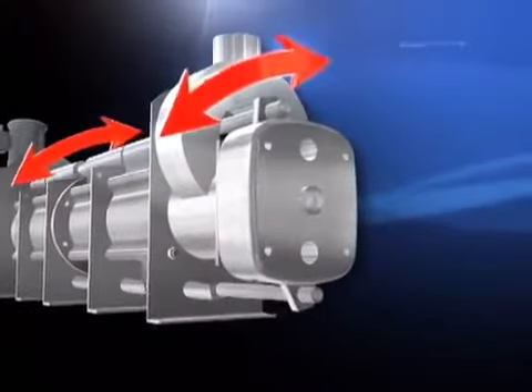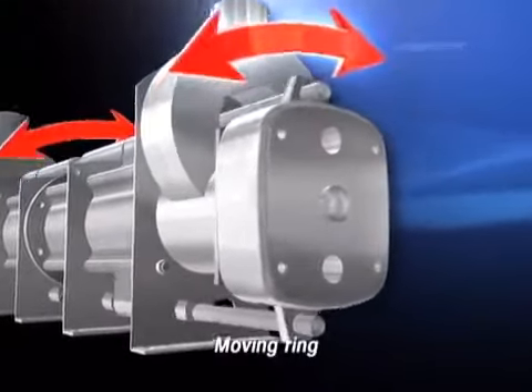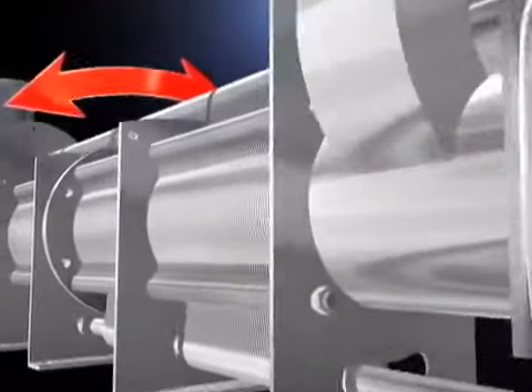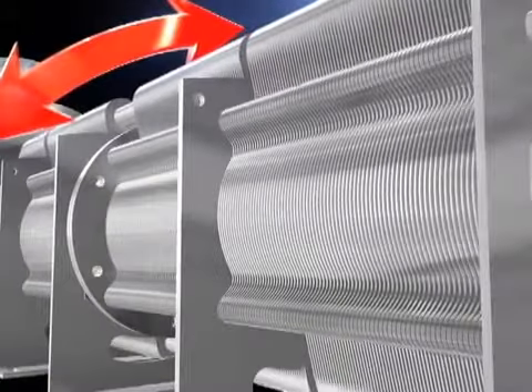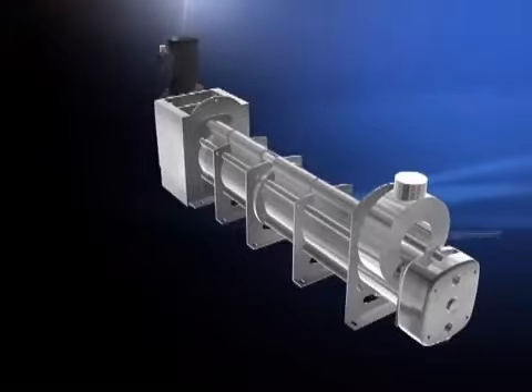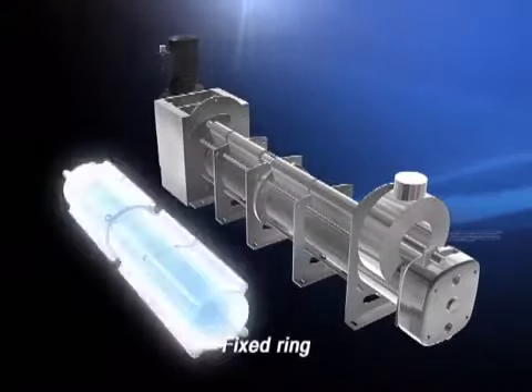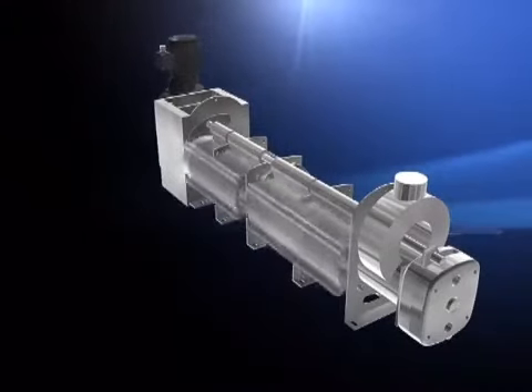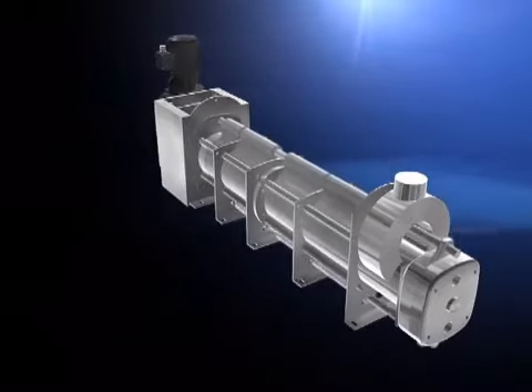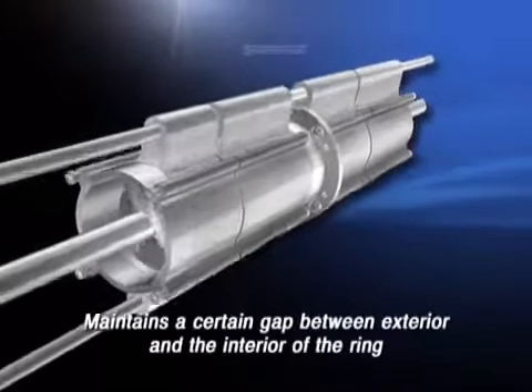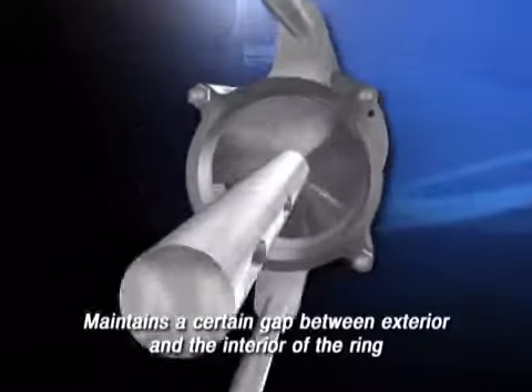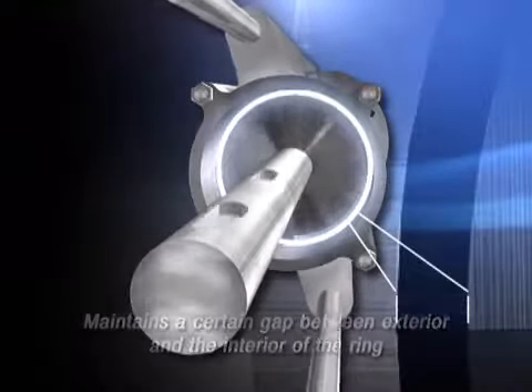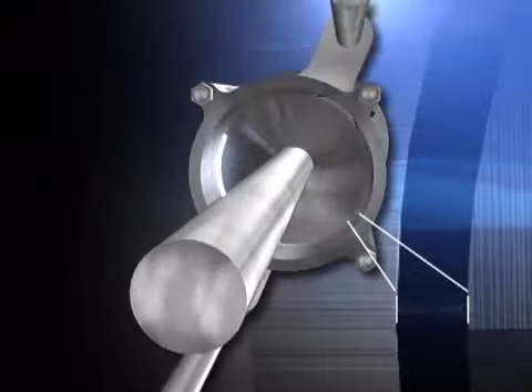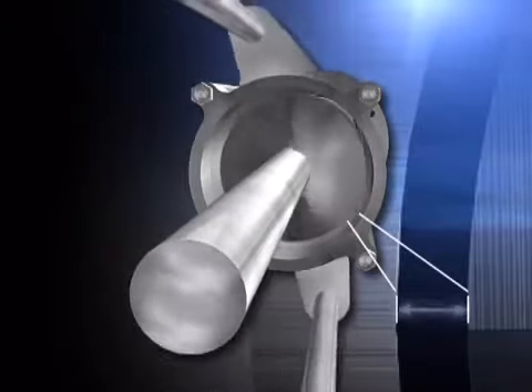Unlike other screw-equipped dewatering machines, the rod-driven moving rings are located at the gearbox on both sides of the screws, and the ring is fixed to a support beam to maintain the shape of the dewatering machine, and the middle of the washers are laminated. This structure maintains a gap between the exterior of the screws and the interior of the ring, preventing wear and tear on the screws and the ring.